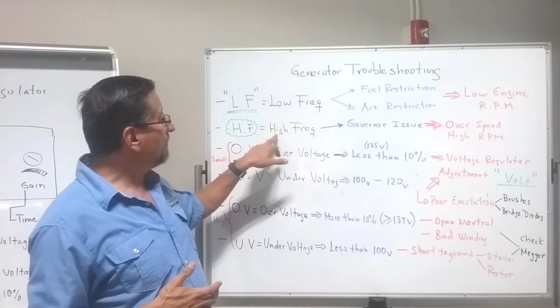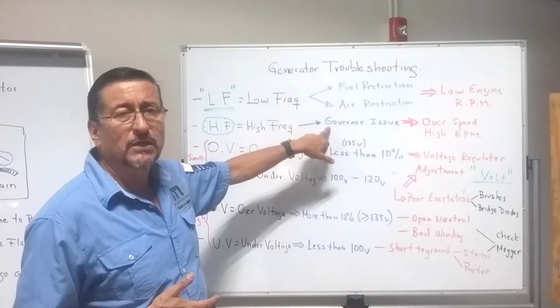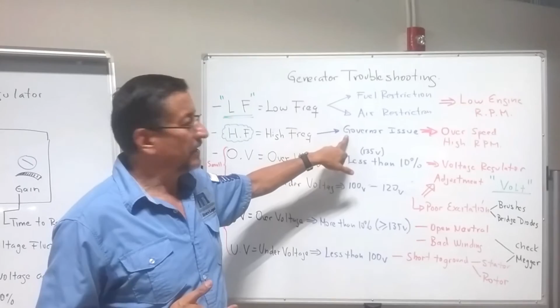Another common problem is HF. HF is high frequency. High frequency normally is an issue on the governor of the fuel injection pump, or the governor of the carburetor if the generator is gasoline. A mechanical problem on the governor produces overspeed or high RPM.